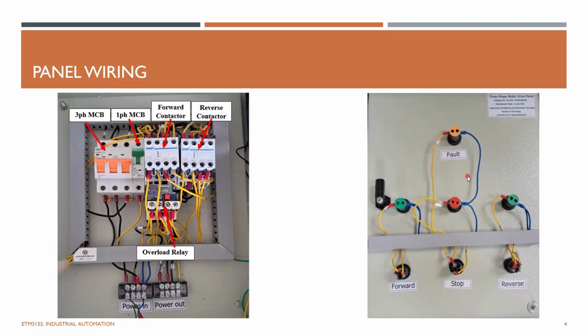On the bottom side of the panel, we have these light indicators. This is for forward, stop and reverse, as well as your momentary push buttons. The four light indicators should be coupled to the neutral, and the other wirings go to your auxiliary contact points via these PVC wire ducts. And the push buttons are also connected according to the wiring diagram given in your lab manual. So you are required to do the wiring from scratch, complete it, and have it verified by the instructor before powering it up.